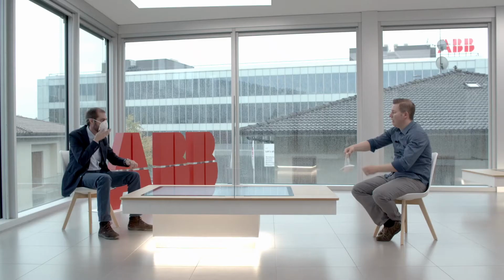Thank you again, Simone. And what do we have to consider when we'd like to connect our system to ground? Well, the main point we have to consider is the state of the neutral point of our AC systems. With reference in particular to electric vehicle charging infrastructures, it is usual for this level of power to have a dedicated medium voltage, low voltage power transformer, so that theoretically we can have both an isolated or a directly grounded neutral point. However, usually this kind of infrastructure is built upon a two-wire isolated DC section with the AC section with a directly grounded neutral point.